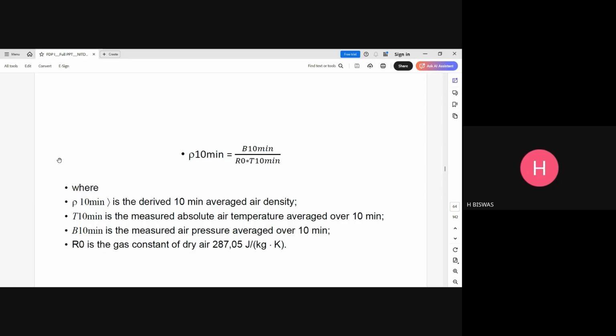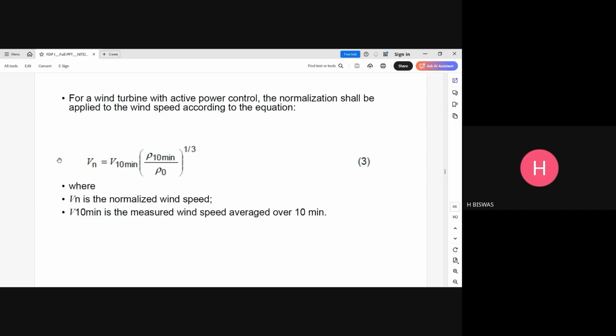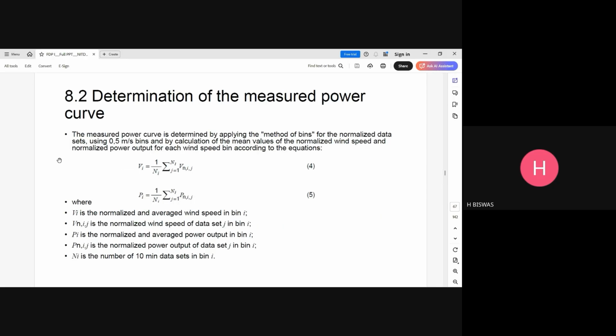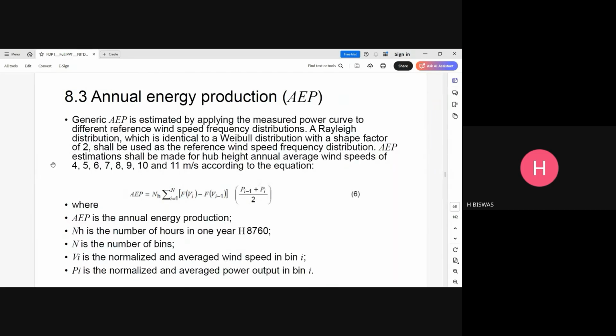There are some formulas for this, just quickly overviewing. Once we have the wind speed measurement, we calculate the wind power available using a specific formula given by IEC, which also takes into account the Betz limit - 0.59 is the factor through which wind can be measured and harvested.